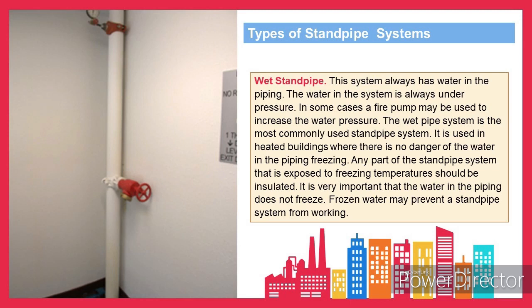It is used in heated buildings where there is no danger of the water in the piping freezing. Any part of the standpipe system that is exposed to freezing temperatures should be insulated. It is very important that the water in the piping does not freeze. Frozen water may prevent a standpipe system from working.